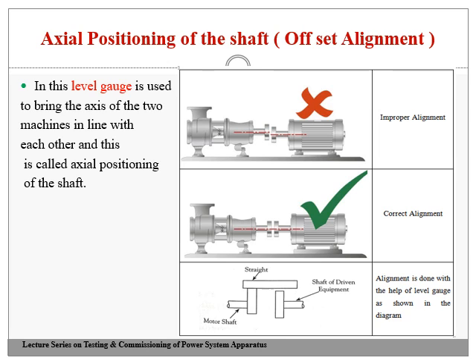You can see the first figure. Let us consider this one as a motor, and this one as a generator. You can see that the motor's shaft is a little bit higher compared to the other machine. Now I cannot couple it, because the two shafts are at different levels. There is a small difference between the height of this one and the height of this one, as seen in the figure. That's why axial positioning comes into the picture. I cannot couple it, so this is an improper alignment.